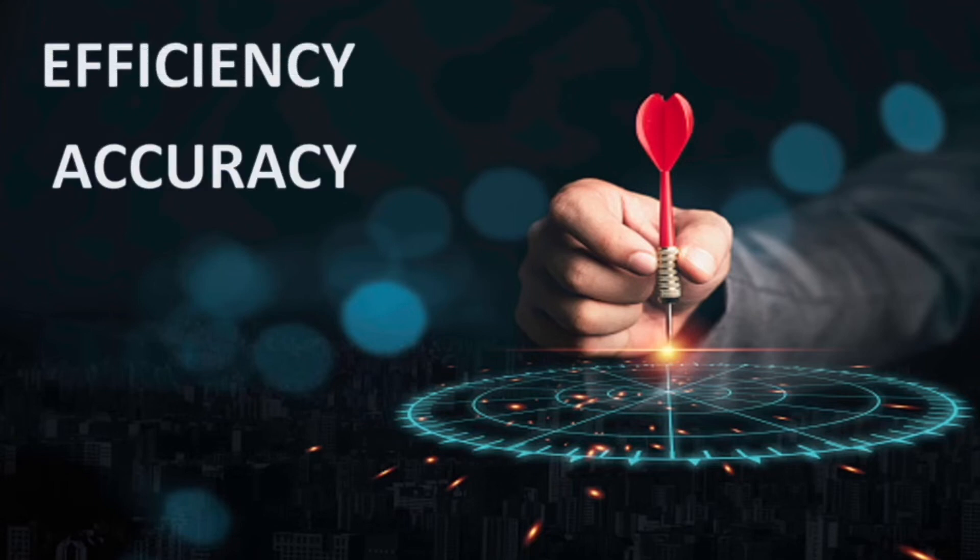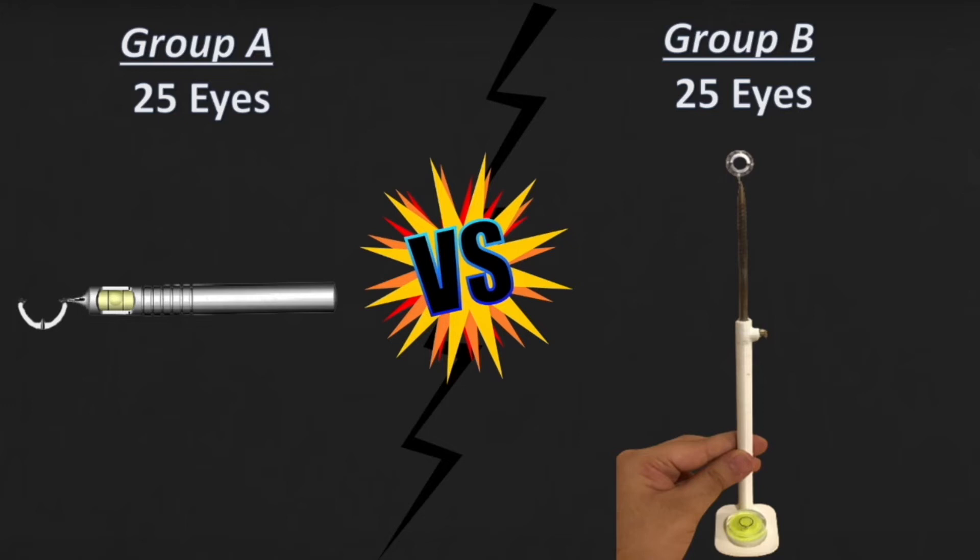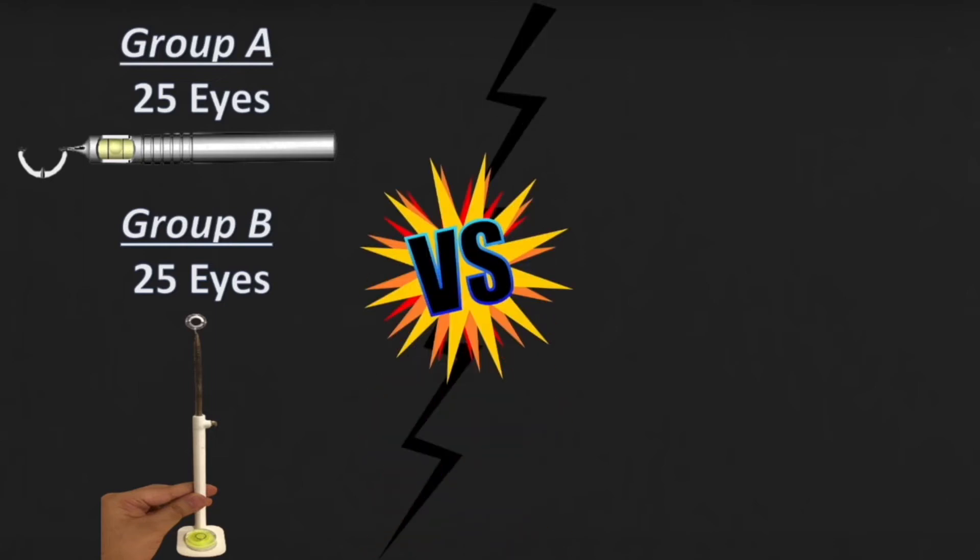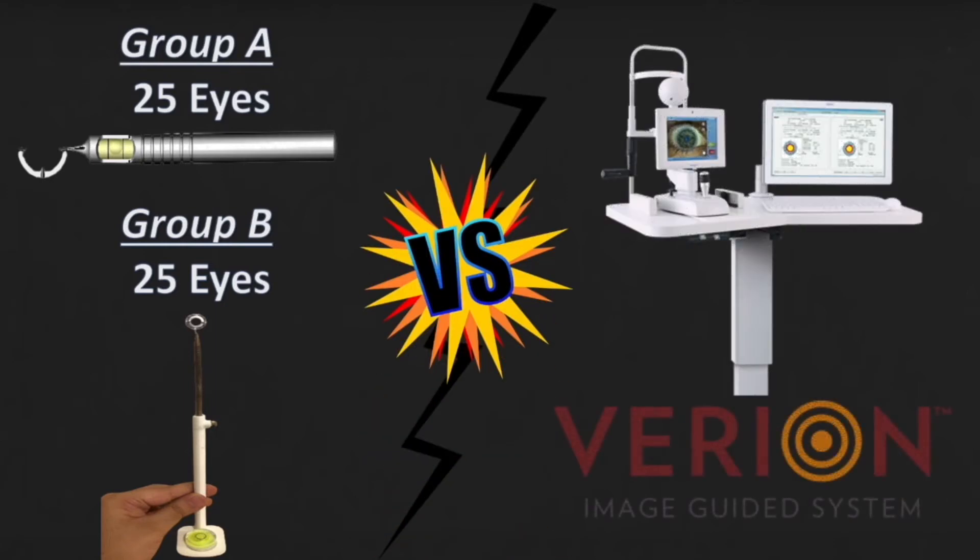Now to study the efficiency and the accuracy of our device, we conducted a simple study wherein Group A, that is 25 eyes, were marked the preoperative axis using the conventional toric marker, and we compared this with our toric marker, 25 eyes. We then took into account Group A, Group B, that is 50 eyes, and compared it with the Verion gold standard image system.